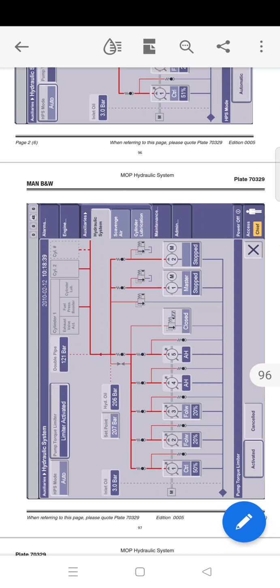Cancellation of the limiter will raise an alarm on the MOP. So guys, when you cancel the limiter, then in case of high torque, this limiter will not get activated and you will not get an alarm. So that will break the pumps and it will be harmful for the engine, gears, chain, etc. So be careful with this. By pressing the pump torque limiter field, a toolbar will appear where the limiter can be either activated or cancelled. Now, when the limiter is cancelled, the electrically controlled swash plates in the pumps are allowed to deflect to the mechanical limitation. Now what is going to happen?